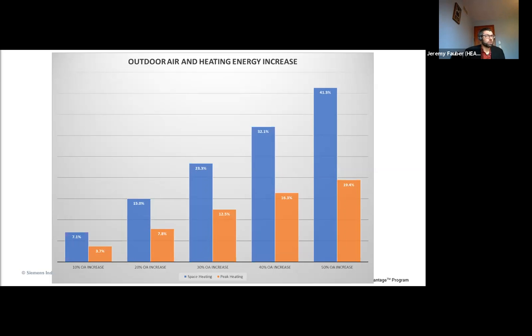This should just really be your central equipment, not your VAVs, as those should still be seeing the same temperature. The only way it would impact that is if you are unable to maintain your typical discharge temperature at a central system. This is going to have the same caveat that I had for cooling: your system type may mean you have to look at one or two things. If you're a gas-fired rooftop unit, you really just need to look at that gas-fired coil. A lot of times, based on my experience, those are oversized based on selection. So you may be able to do a 50% increase in outdoor air for heating, but not cooling.